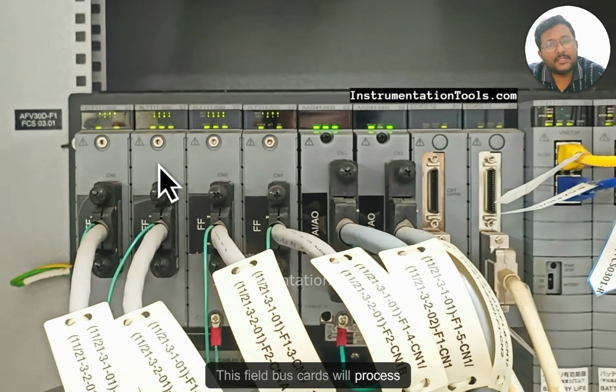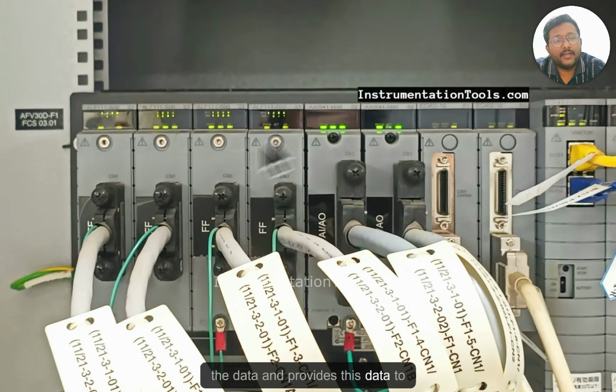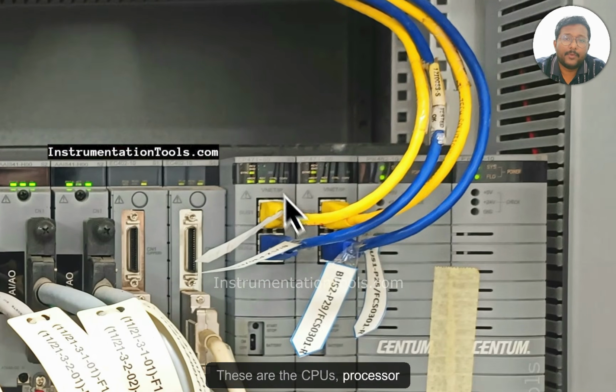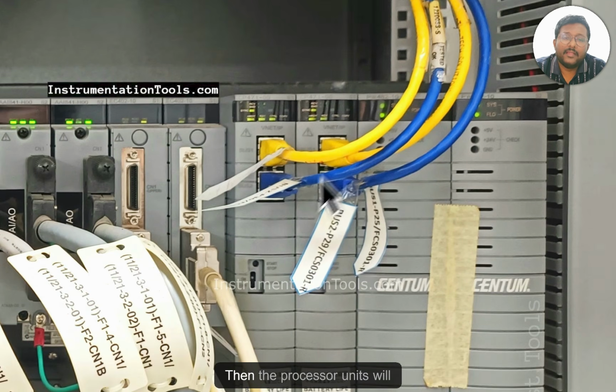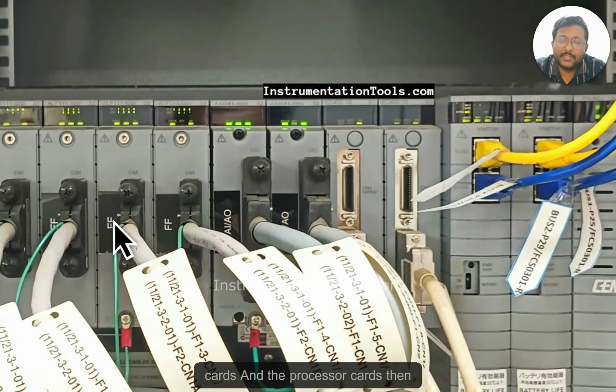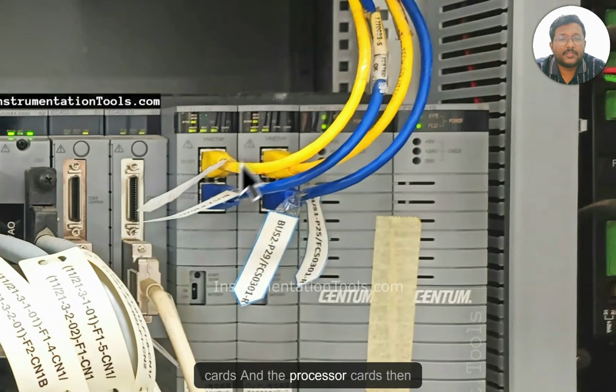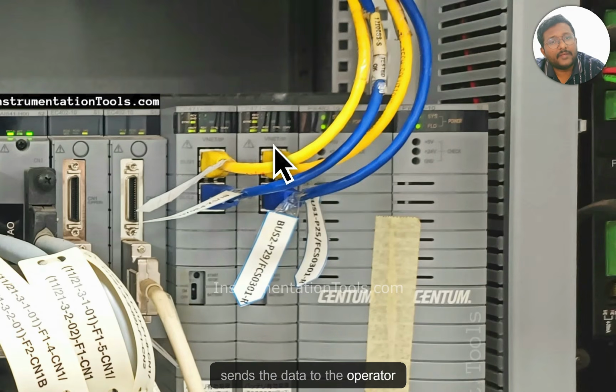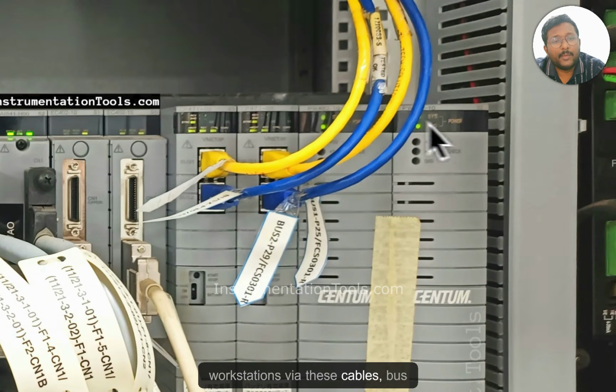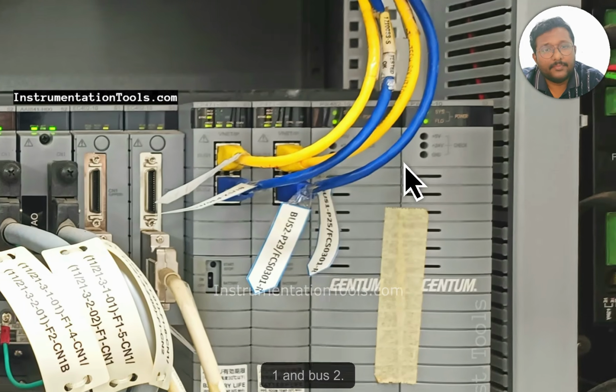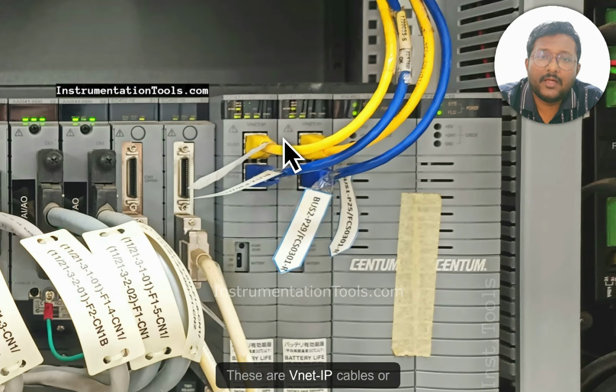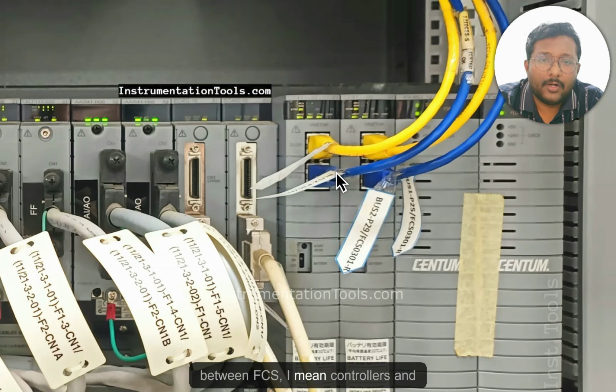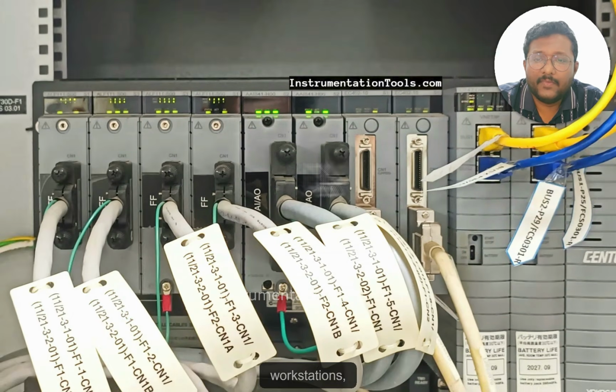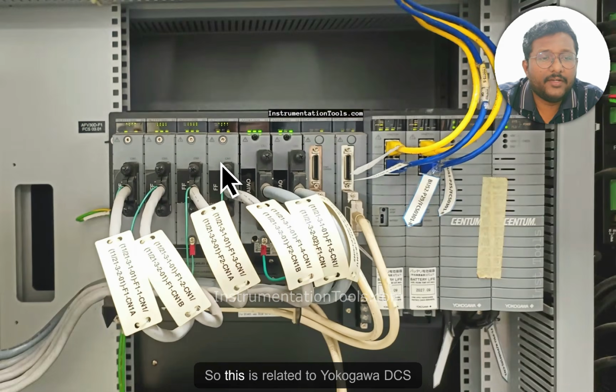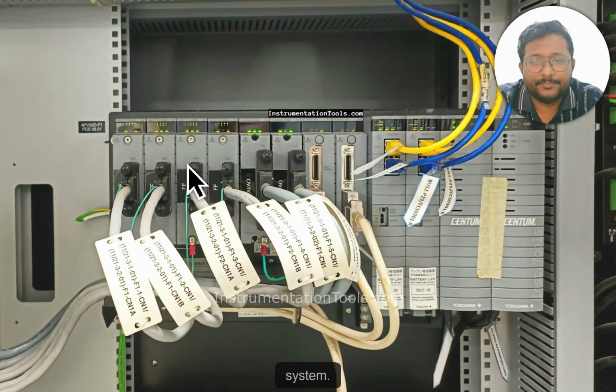Fieldbus cards will process the data and provide this data to the CPUs. These are the CPUs, processor units, right? Then the processor units will receive the data from the fieldbus cards, and the processor cards then send the data to the operator workstations via these cables, bus 1 and bus 2. These are V net type cables or Ethernet based cables for communication between FCS, I mean controllers, and workstations in simple terms. So this is related to the Yokogawa DCS system.